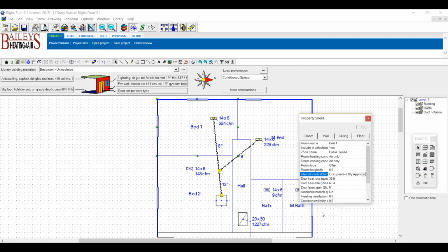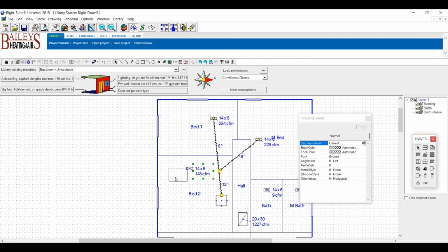And this is one reason people get in trouble when they go in there and say, oh, it's a bedroom, it only needs a 6-inch duct or a 7 or an 8. It may need a 9 or a 10. So I took the load away. And if you don't add the loads in when they're there, say the guy does have a terrarium with a snake in it, you need to figure that in, or it won't cool or heat correctly. So now I got 12-inch, and here in California we're concerned more with cooling than heating, because we're a pretty mild climate in the winter.